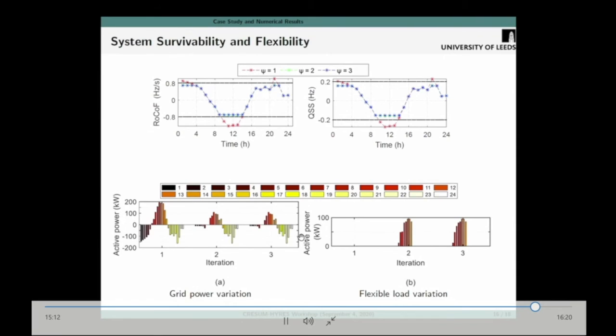In the lower diagram, we see the power schedules of the grid power variation on the left, and on the right, the flexible load. At each iteration, we observe that the power is being decreased to ensure that the violations with the security limits are adhered to. However, how is this done? There is a use of flexible loads in the system, as we notice an increase in flexible loads in iterations 2 and 3.